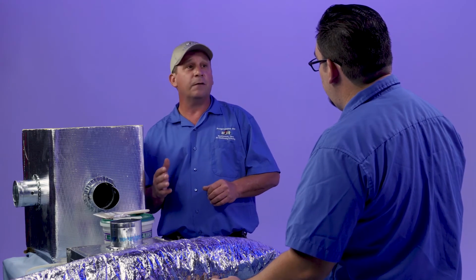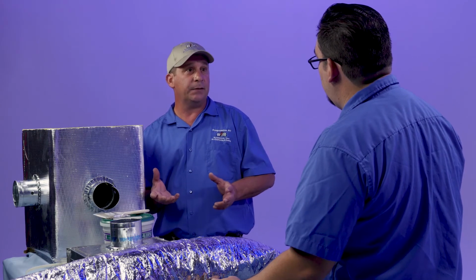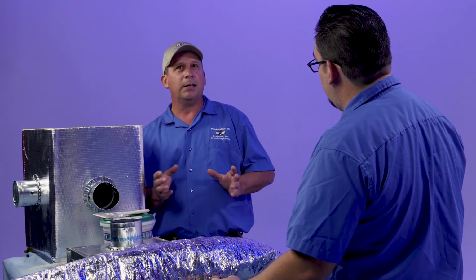A lot of homeowners get these MERV pleated filters, thinking more is better, and have 3, 4, or 5 of them in a house. They do a good job trapping dirt, but they restrict a lot of the airflow. It's called high static. The air handler, the indoor unit, needs enough air getting into it. If it can't get enough air into that equipment, it can't deliver the amount of air out to the registers.